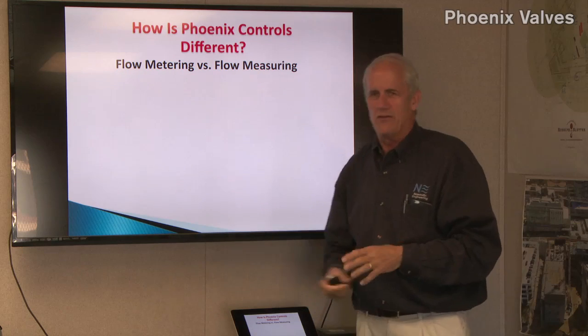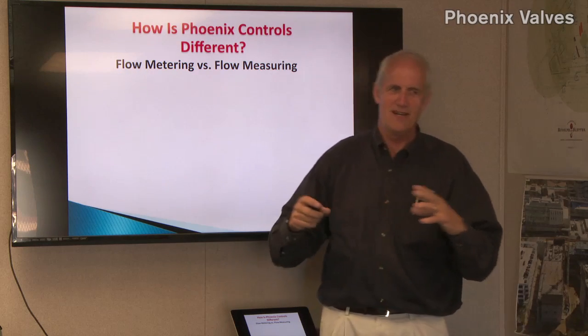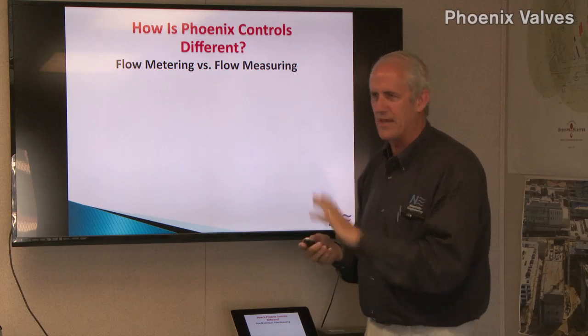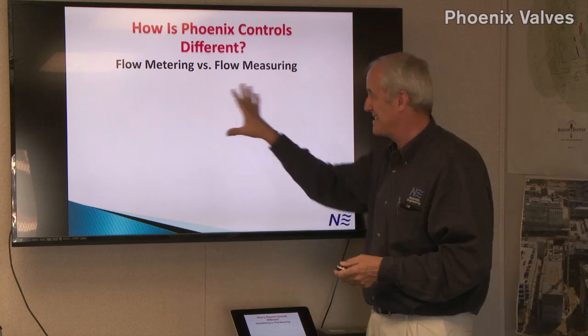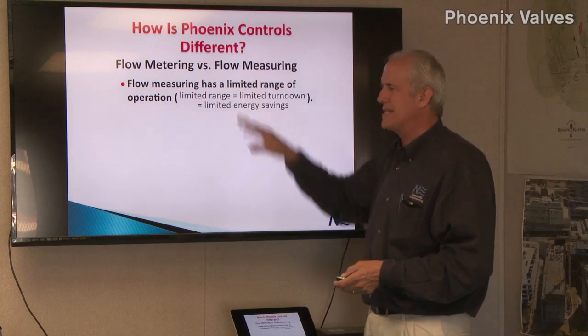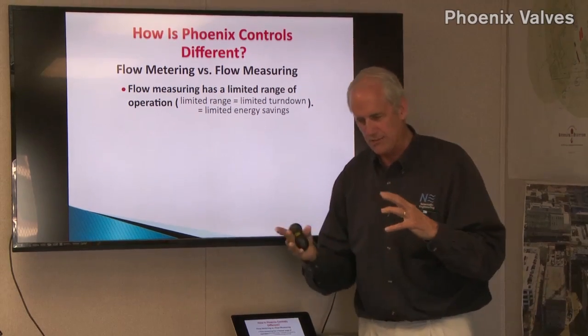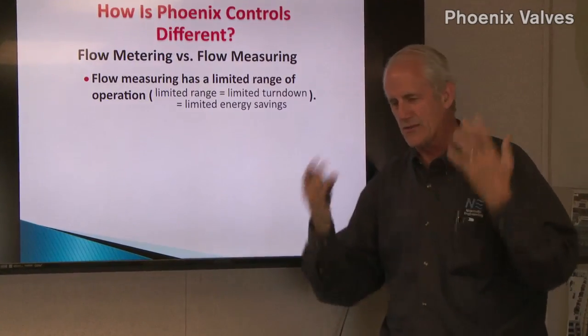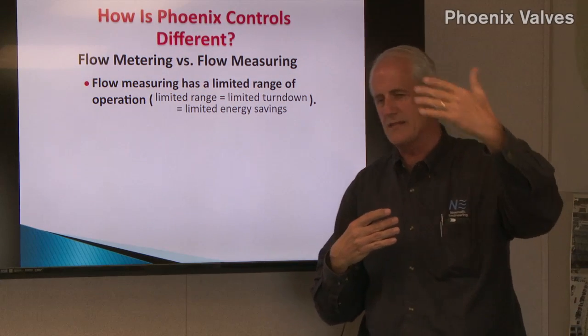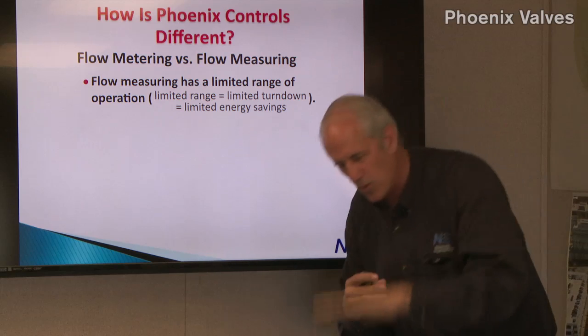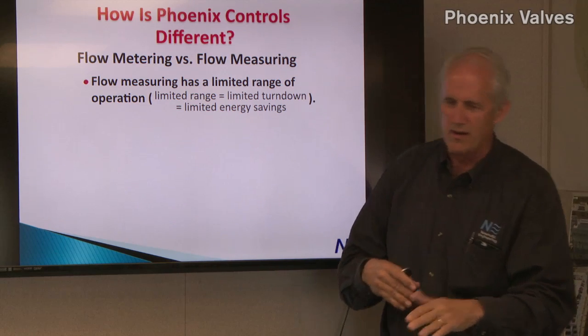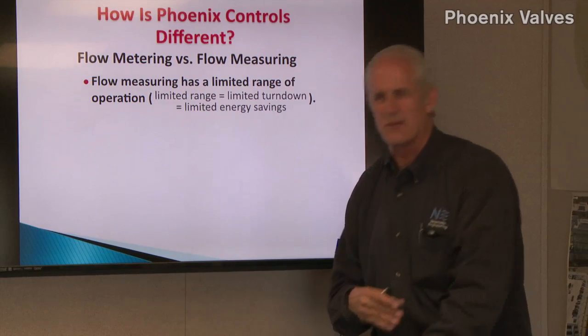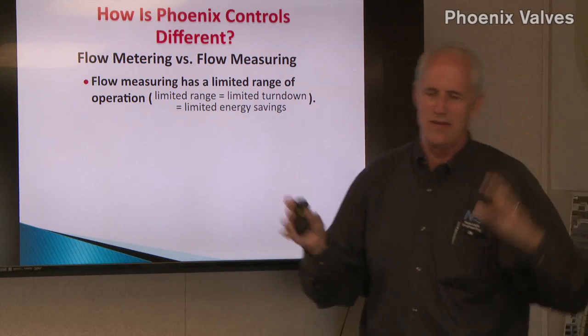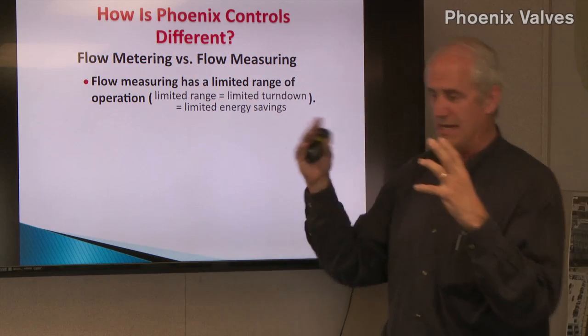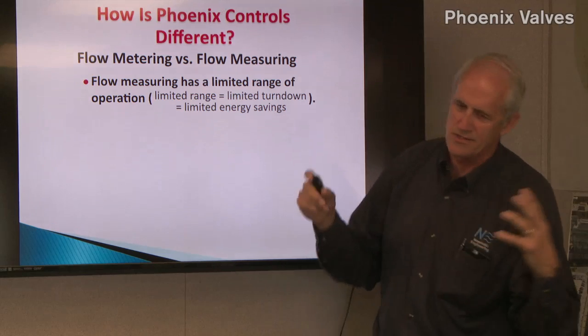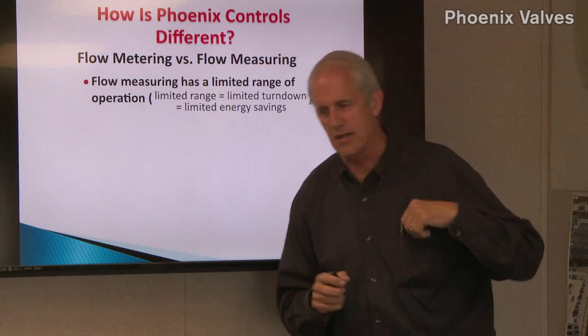We don't measure the flow, we meter the flow. What? You don't measure flow? And it actually ends up being better in this application. So if you're used to working on a VAV box, this thing works in a different way. Flow measuring has a limited range of operation because the velocity pressure varies as the square of the velocity, which is to say when your velocity drops in half, the signal you're measuring drops to 25%. When your velocity drops to a quarter, the velocity pressure drops to 1/16. So you're down in the super low range. If you're trying to measure 6%, you probably have a 1% error on your transducer. So VAV boxes really start messing up if you try to control them with any kind of turn down.